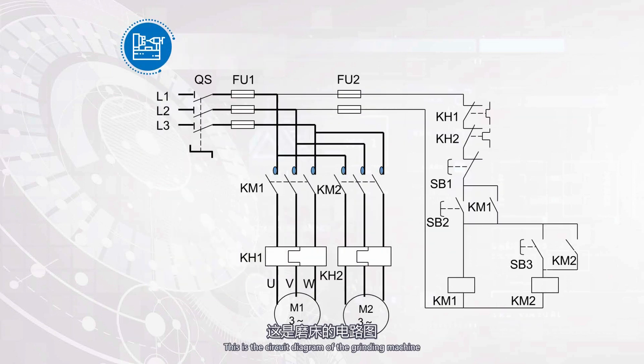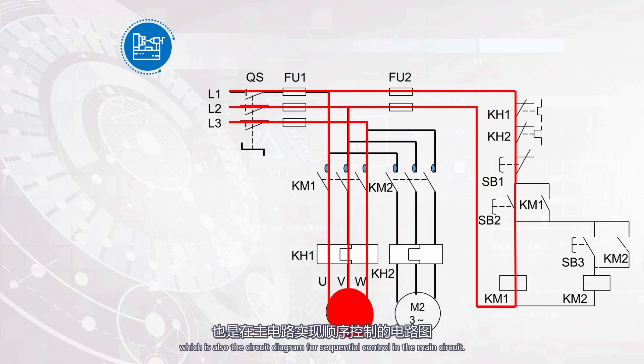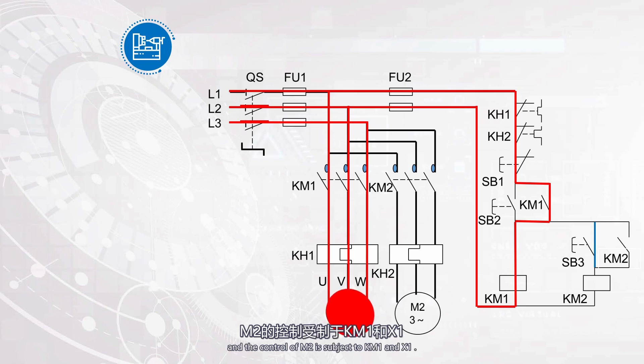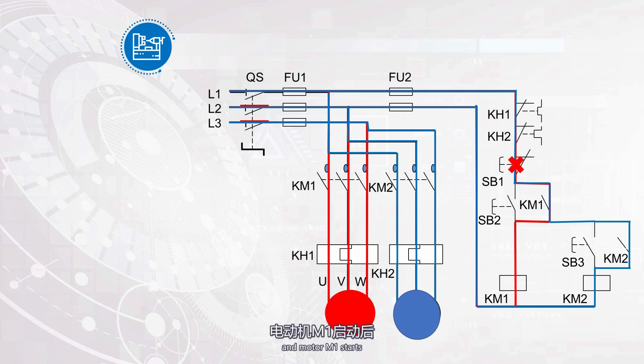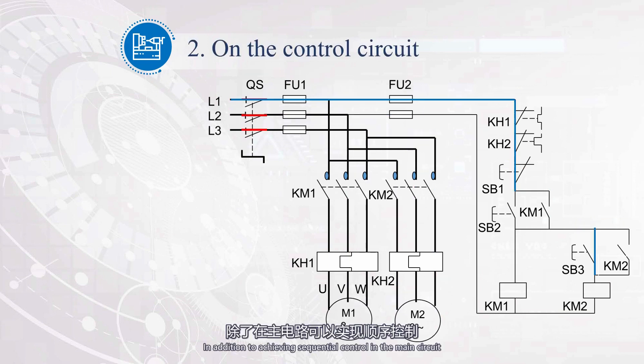This is the circuit diagram of the grinding machine, which is also the circuit diagram for sequential control in the main circuit. The control component of M2 is the contactor KM2, and the control of M2 is subject to KM1 and KM2. Only when KM1 is powered on and motor M1 starts, can motor M2 be started by closing KM2. In addition to achieving sequential control in the main circuit, it can also be achieved in the control circuit.